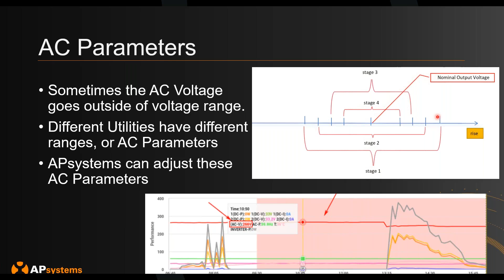However, it is possible for us to expand those allowable parameters to basically tell the microinverters, oh, you see 266 volts, you can actually operate a little bit higher. So that's something we can do, go into the microinverter and expand those AC parameters. That's one thing we often recommend customers do if they see microinverters cutting out in this manner, it's possible it's an AC parameter setting we need to adjust. So give our tech support a call or send them a ticket, and we can observe if it's an AC parameter issue we can expand so the microinverters can function.